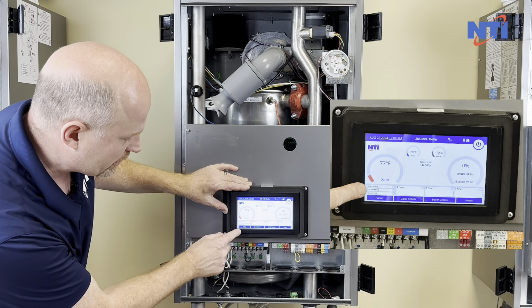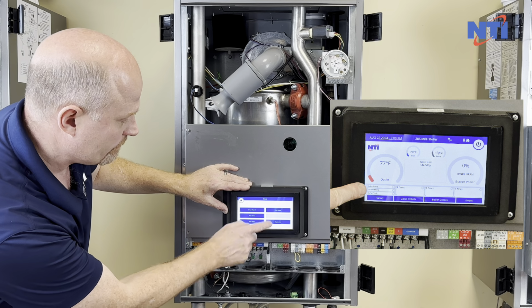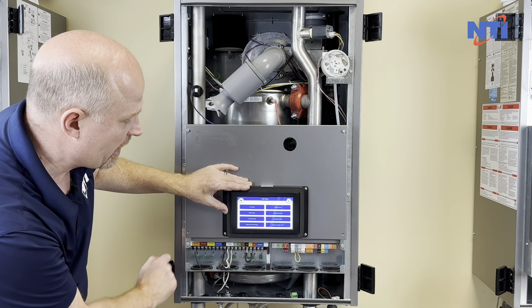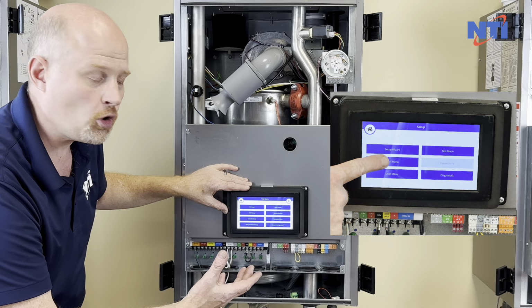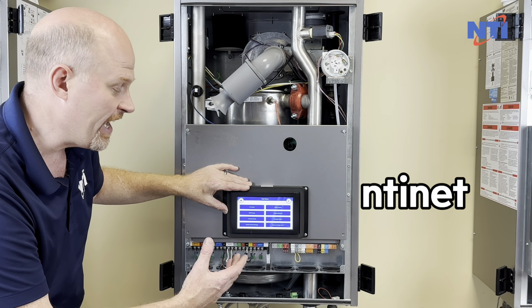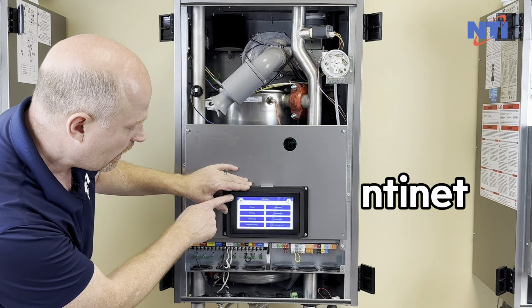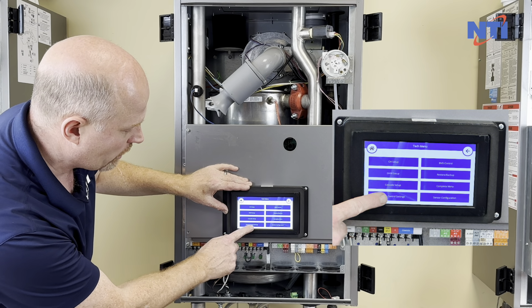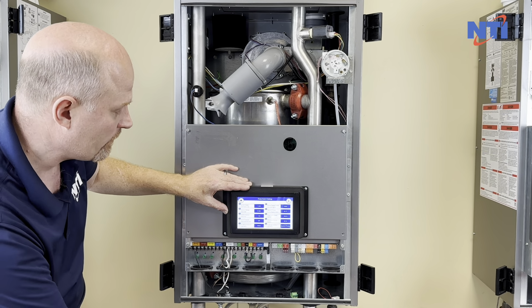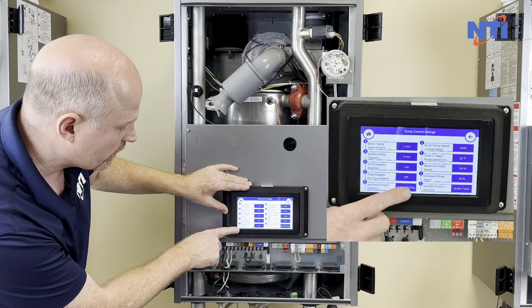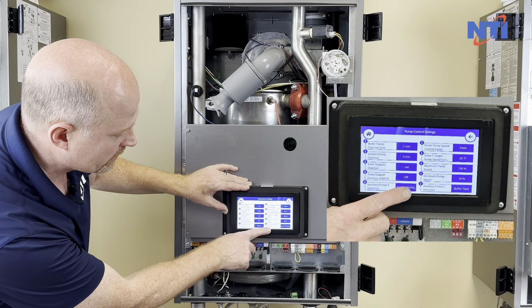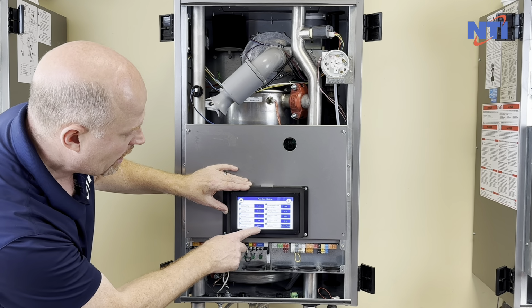To get to the pump functions, you're going to start by hitting Setup. Then you're going to go to Tech menu. If you're asked to log in, the password is NTI net. Type that in and press Enter. Now that we're on our Tech menu, we want to go to Pump Control Settings. And at the very bottom here, you have Auxiliary Pump Selection 1 and Auxiliary Pump 2 selection.